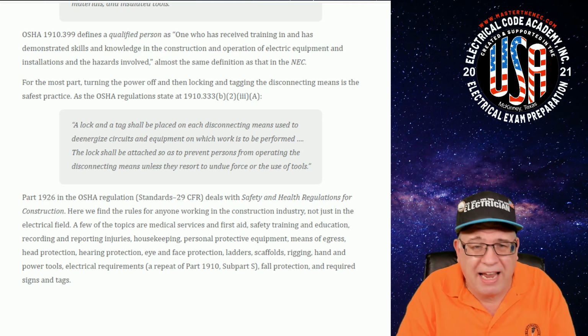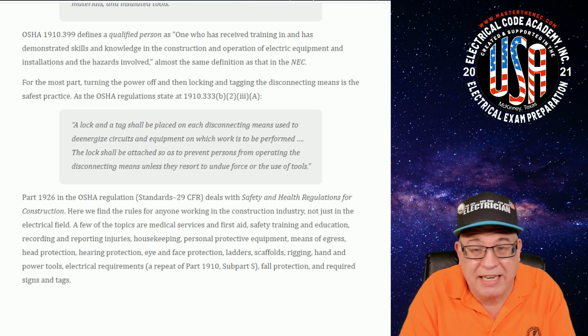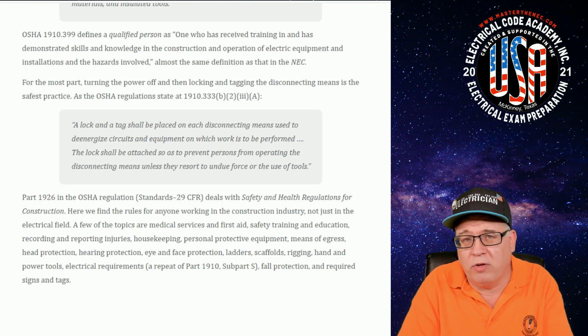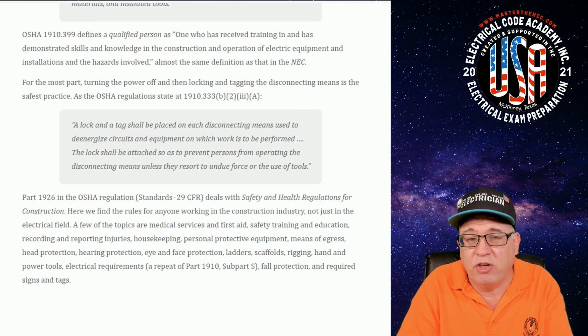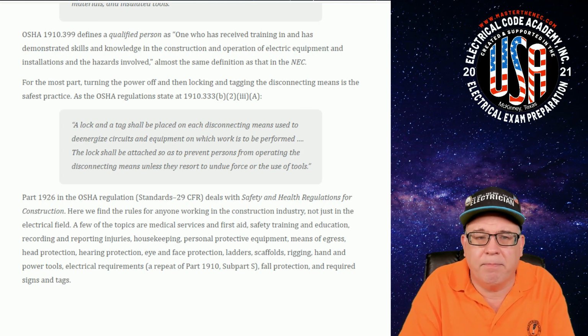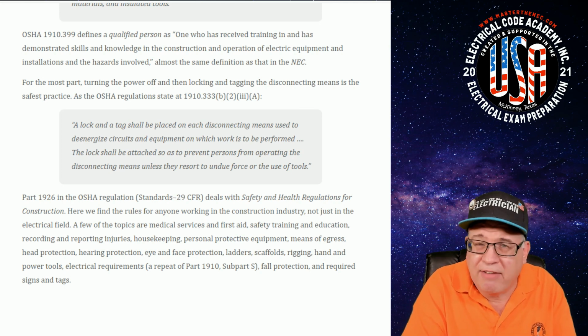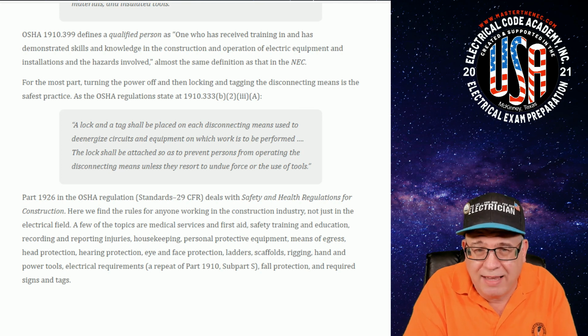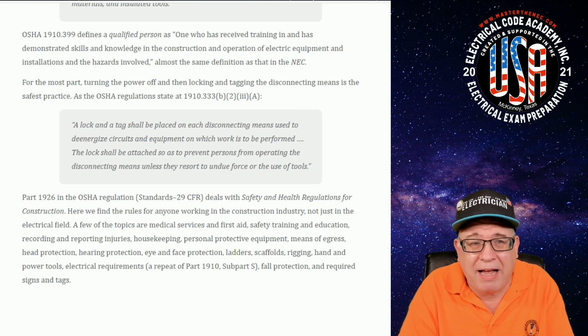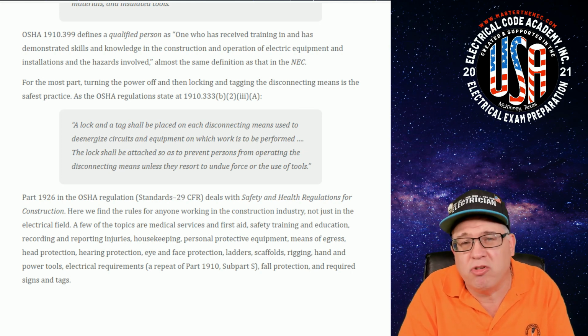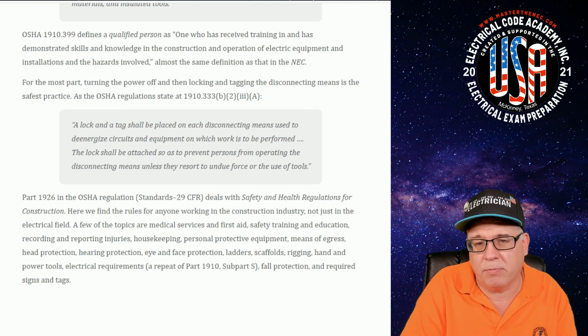So you have a disconnect. It's usually built. You need to have one if it needs to meet the rules of 110.25, and you're utilizing that for the lockout tagout, then you have to make sure that it can receive the lock and it does lock it in the open position. And that is about the safest practice that you can get to work on a circuit, okay?